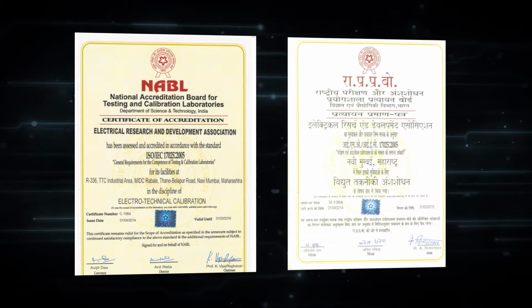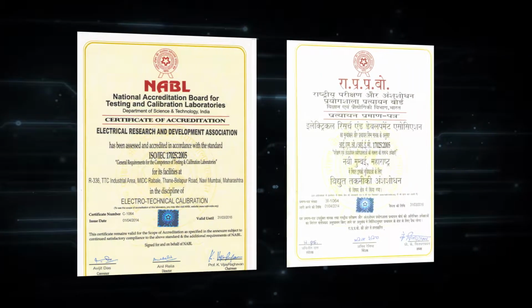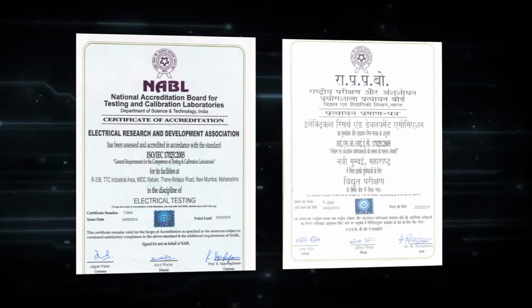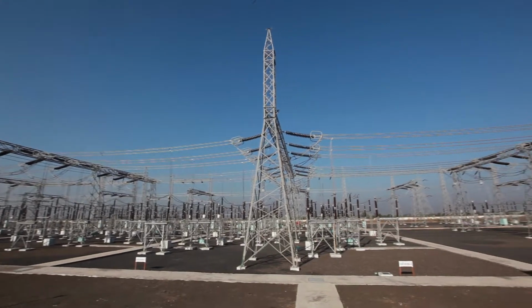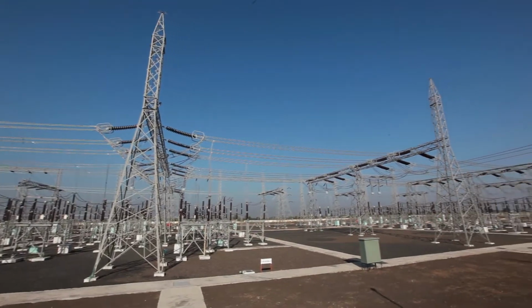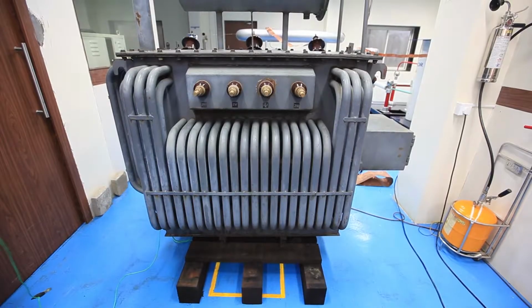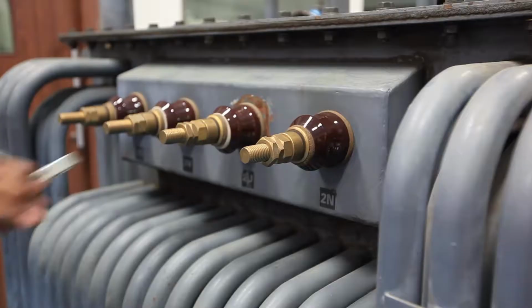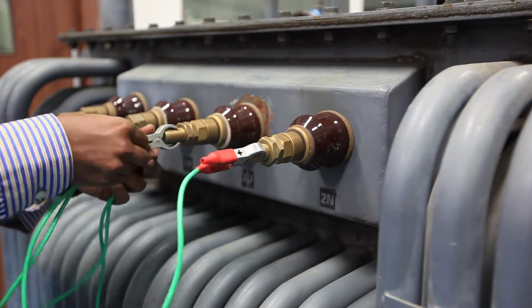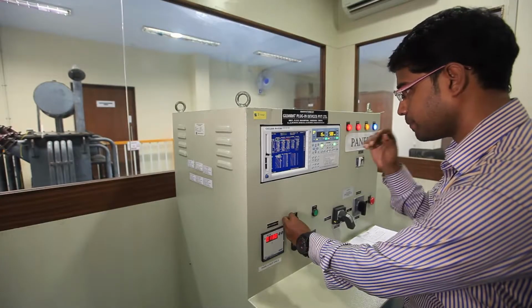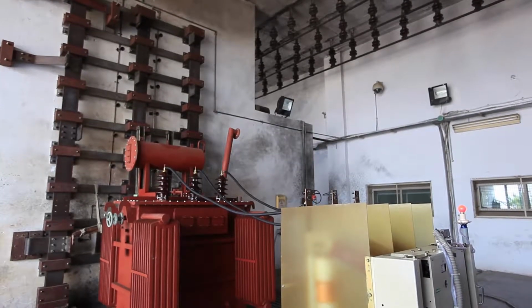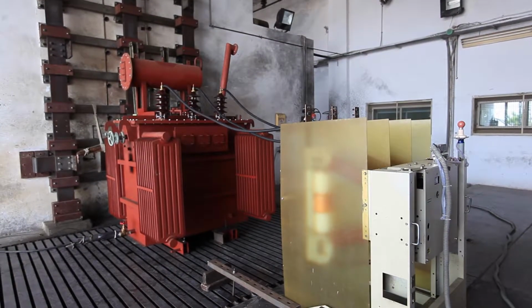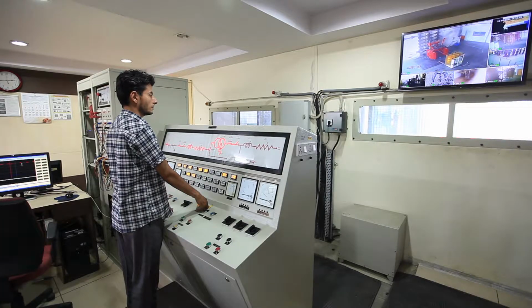ERDA West is accredited by NABL Government of India for testing and calibration at laboratory as well as on-site. It is also recognized by utilities, PSUs and several other agencies. The quality of 33 kV class distribution transformers, 200 kVA, can be ascertained through type tests.